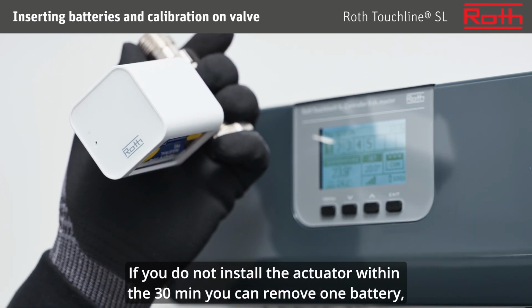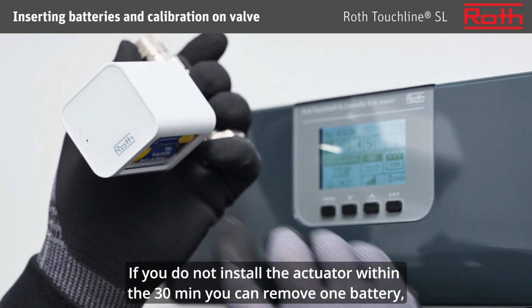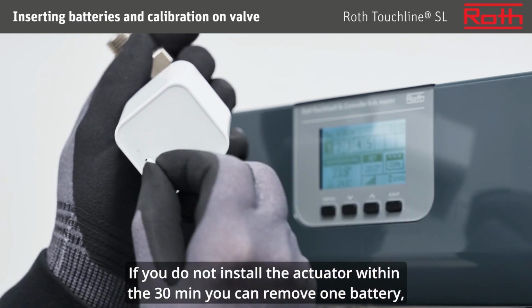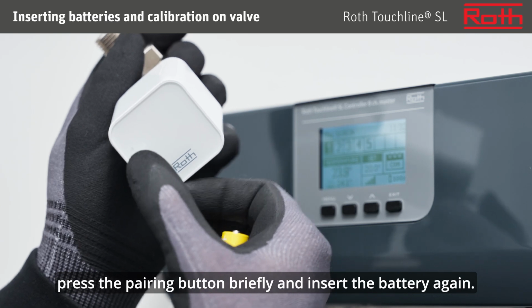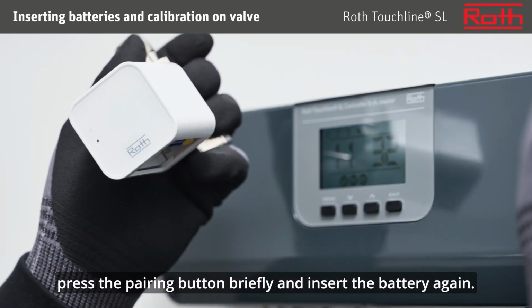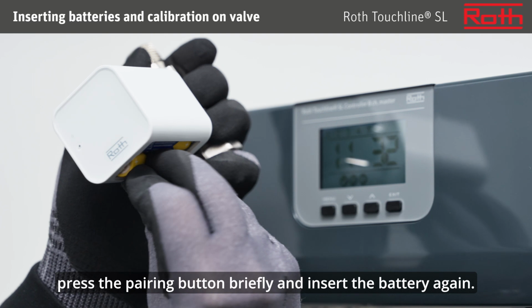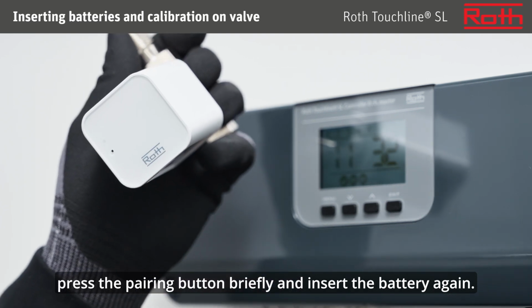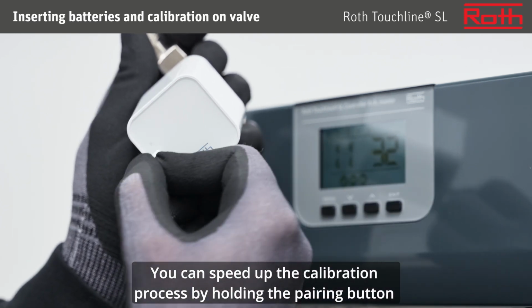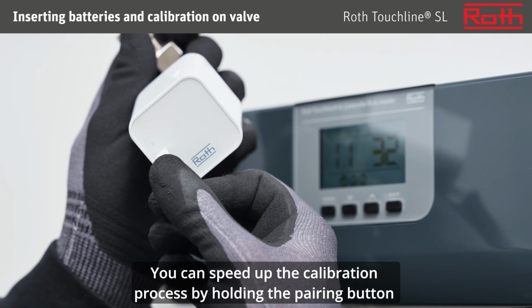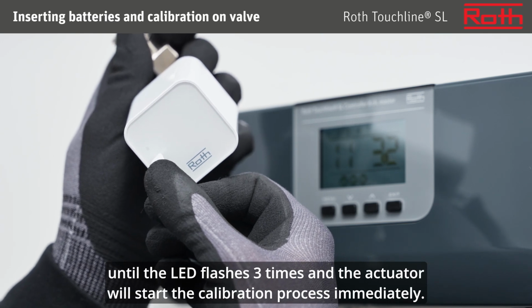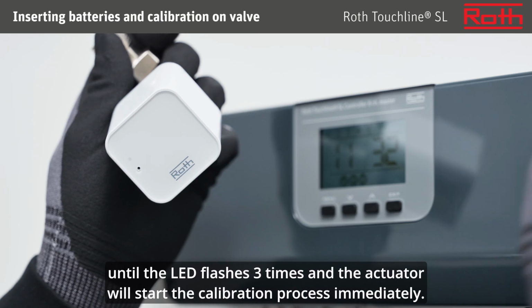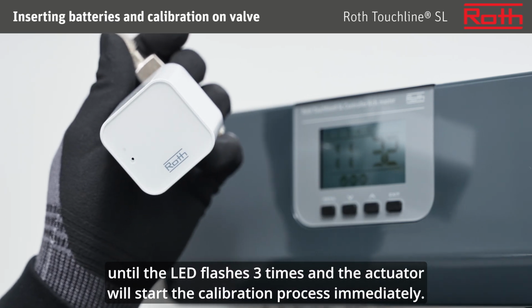If you do not install the actuator within the 30 minutes, you can remove one battery. Press the pairing button briefly and insert the battery again. You can speed up the calibration process by holding the pairing button until the LED flashes 3 times, and the actuator will start the calibration process immediately.